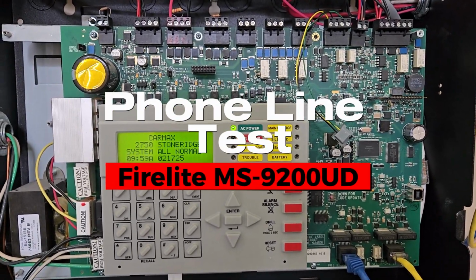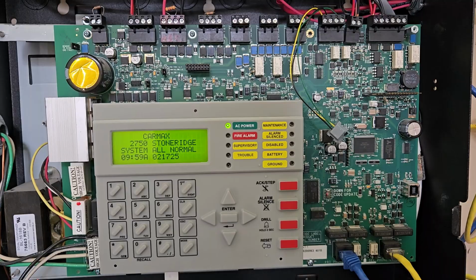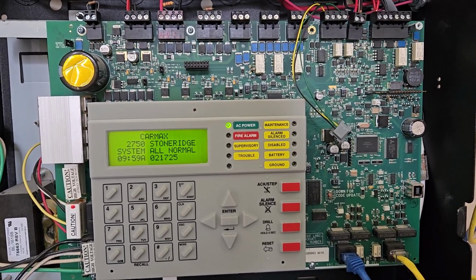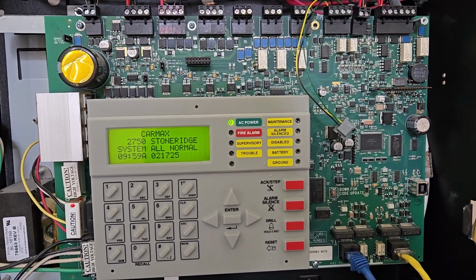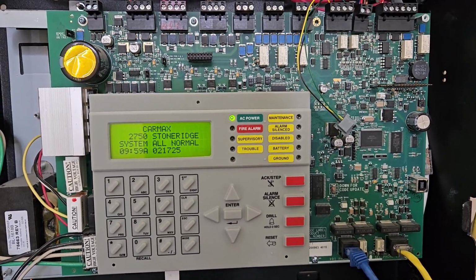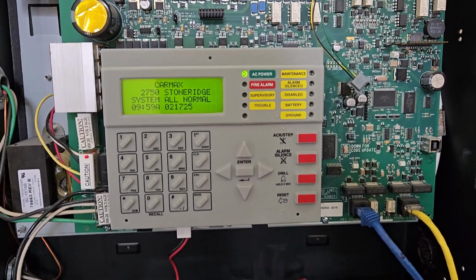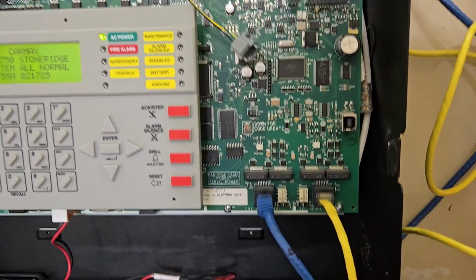Hello, in this video I will be showing you how to test your phone lines. We will be doing a disconnect test of the phone line to verify we get a trouble signal to the fire panel. We will identify your phone lines on the board.